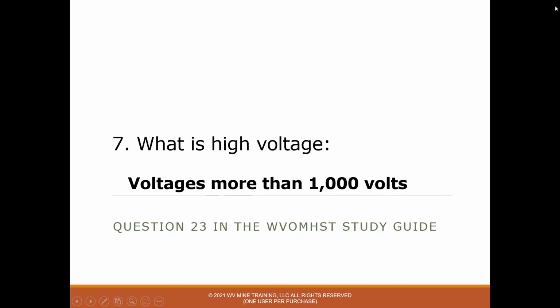Number 7, what is high voltage? And that's voltages more than 1000 volts. So anything more than 1000 is high voltage. And the common voltages that we have at the mine are 480, 575, 995, 2400, 4160, 7200. So we have classes of voltages in those increments that I just mentioned. So high voltage is going to be 2400 volts, I think the first high voltage equipment that we would come to.